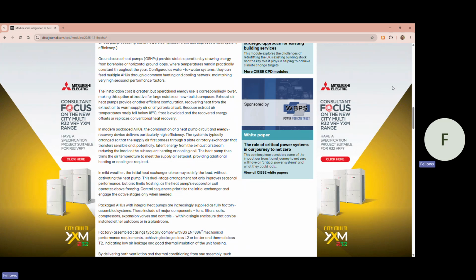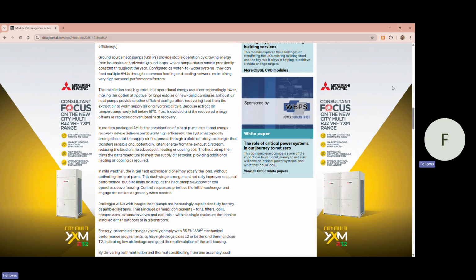The system is typically arranged so that the supply air first passes through a plate or rotary exchanger that transfers sensible and potentially latent energy from the exhaust air stream, reducing the load on the subsequent heating or cooling coil. The heat pump then trims the air temperatures to meet the supply air set point, providing additional heating or cooling as required. In mild weather, the initial heat exchanger alone may satisfy the load without activating the heat pump.